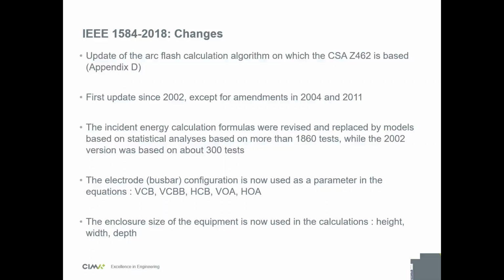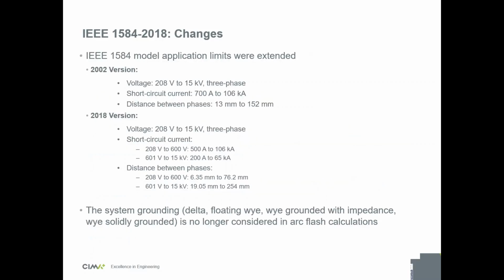And now there's also a big change: the enclosure size of the equipment is now used in the calculations. That is the height, the width, and the depth of the cell of the equipment or the panel enclosure. The application limits were a bit extended compared to the 2002 version. The voltage has not changed. IEEE 1584 still applies from 208 V to 15 kV, 3-phase only. The short circuit current lower limit has been lowered to 200 amps, and it goes up to 106 kA, and the distance between phases has been extended too. So the standard now covers more cases than before.